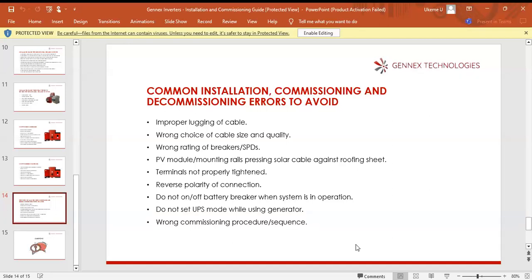Wrong PV module mounting rails pressing solar cables against the roofing sheets, which I mentioned earlier on, can introduce a leakage to a high voltage system. It may not even cut the cable. Based on experience, it may not cut it. There is insulation on the body, but because it's pressing, there will be a transfer. There will be leakage, and then the inverter could respond to this.